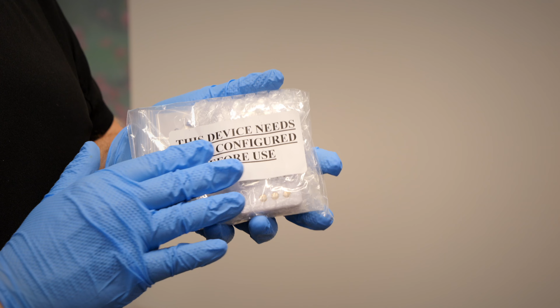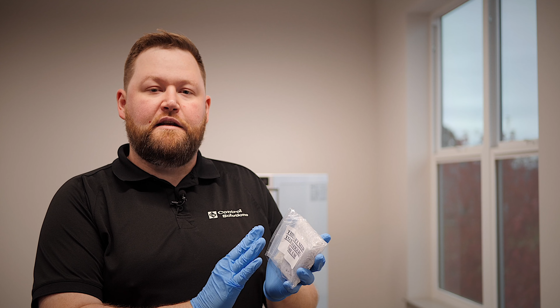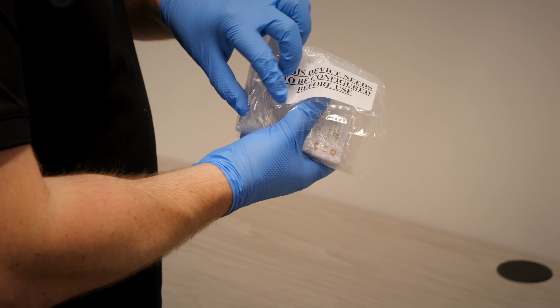Please note that whatever you send us will be included back in each one of these bags. Each device will come packaged by itself with its included accessories and a new calibration certificate. We've also included on the front a sticker letting you know this device needs to be configured for use, since it just went through our testing process and we need to validate our settings before putting it back into vaccine monitoring. I'm going to simply open up the adhesive package.